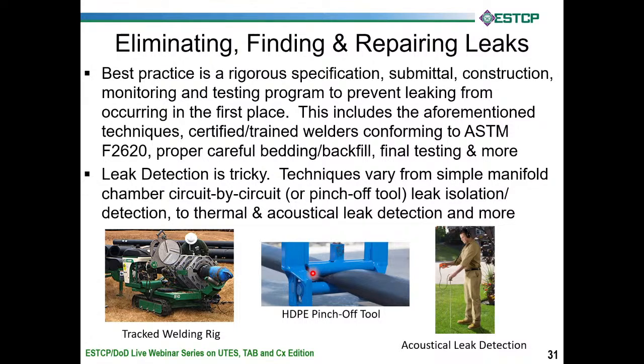And if there's a leak and you don't have a manifold chamber where you can isolate a section, that's a tool you have to use sometimes. But what happens if there is a leak? Leak detection is tricky, that's for sure. If you've got these manifolds that Brandon talked about earlier and these big underground vaults, you can isolate it circuit by circuit until that pressure transducer that we talked about before, or that hydrostatic pump, does not need any makeup anymore. And at that point, you know which of the branch lines.